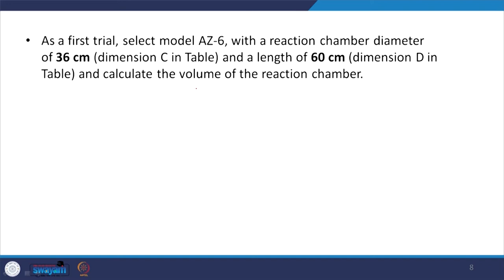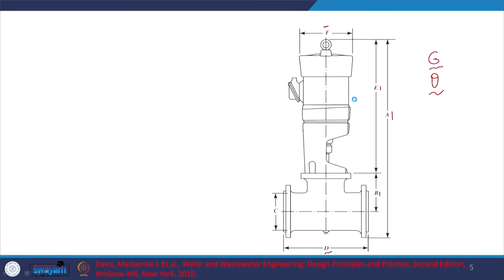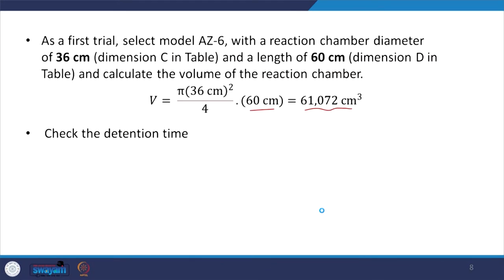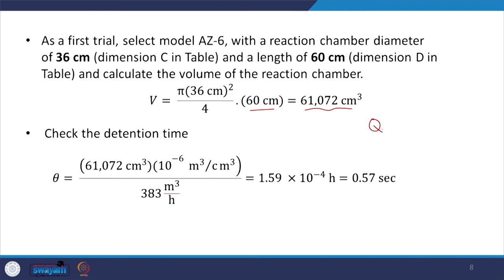We are selecting dimensions C and D inside the chamber. We can calculate the chamber volume as pi·D²/4·h, and we get the relevant volume from the table. Then the retention time: theta equals V divided by Q. Playing around with the units gives us 0.5 seconds. For adsorption coagulation we want theta to be 0.5 to 10 seconds, so 0.5 seconds is more or less fine.